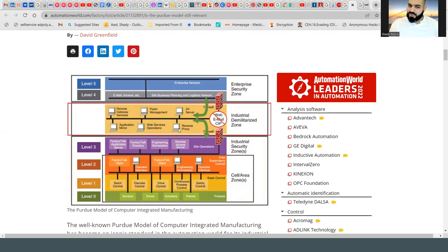So they opened the door for connectivity from this network, which used to be air-gapped. Air-gapped means it was completely isolated. And we connected it to our enterprise system, where my manager is sitting, the IT people are sitting, or maybe the CFO, the guy who looks at financial settings, the sales team, because they wanted to know how many products we sold this week and all the stuff. But these guys also are connected to what? To the internet, right? So we have these guys at the enterprise level, individuals sitting there, connected to the internet. And if someone compromises their machine, because they are also connected to this system, their computer now becomes the gateway for opening the door for connection to our PLC system.